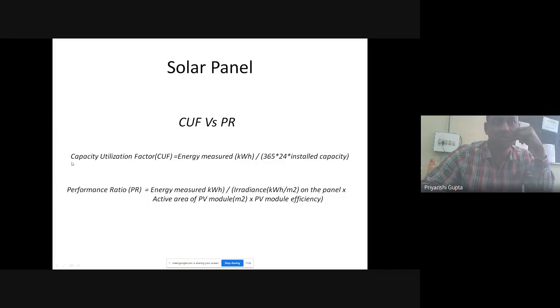The capacity utilization factor we cannot control because it depends on natural phenomena, that is the availability of irradiance. But the performance ratio is in our control, and it demonstrates our efficiency and maintenance practices - how well we maintain the plant and how well we work, the performance ratio will always tell you.